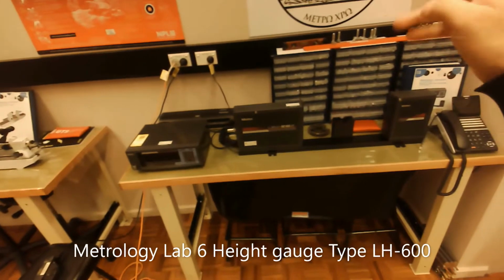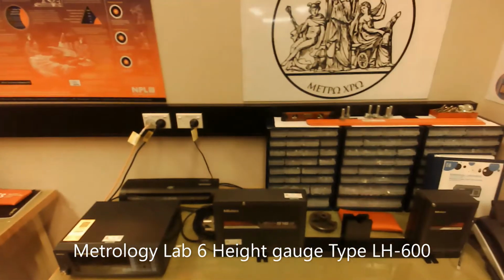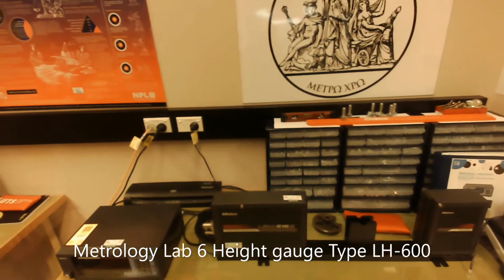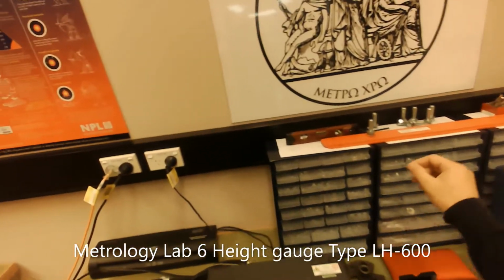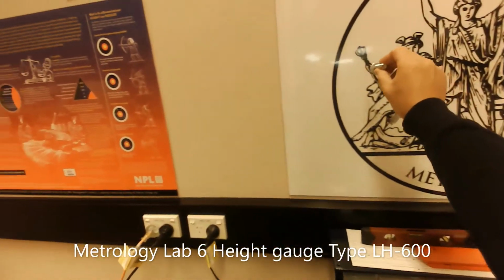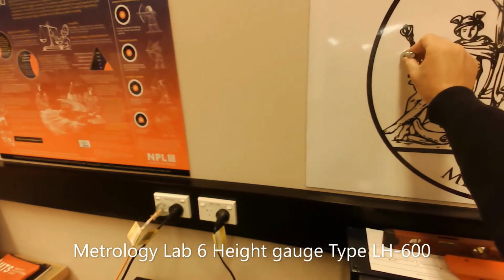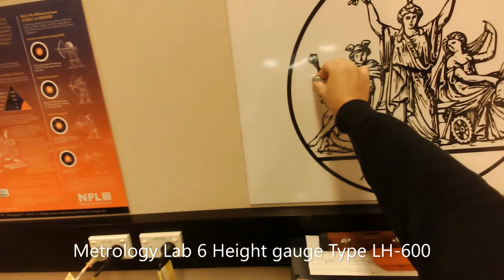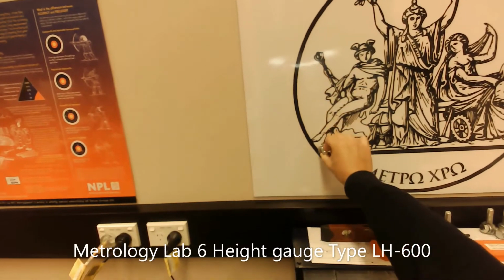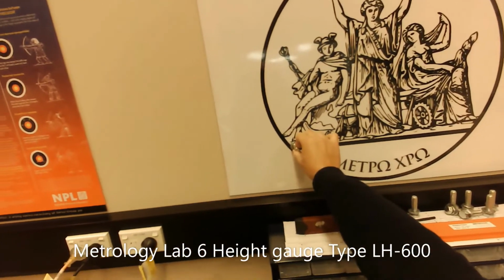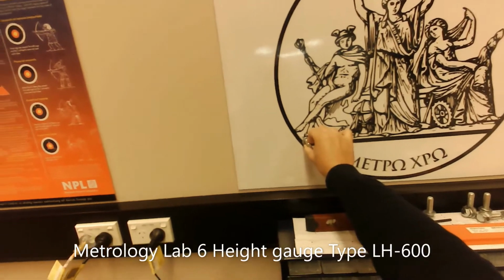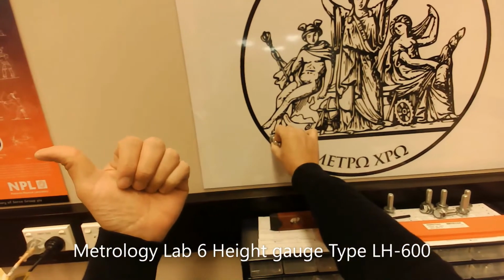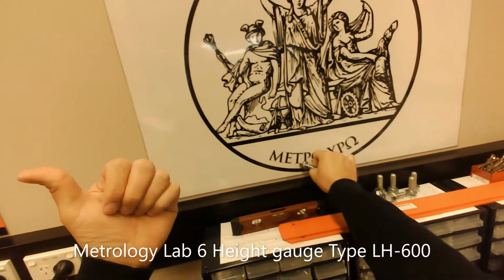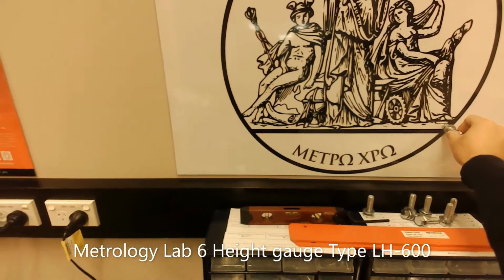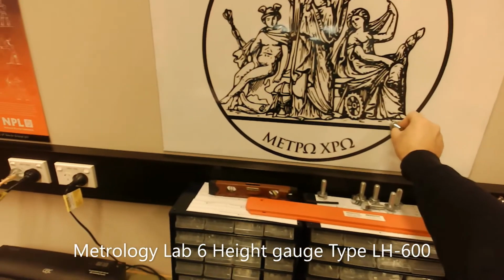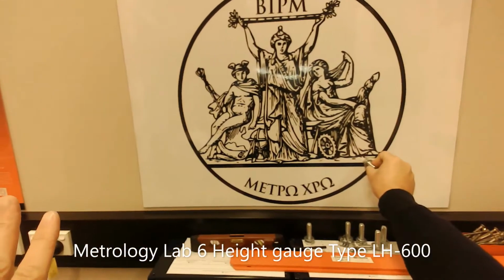Now, I usually use this image to show the student the movement we need to do for the probe. So what we're going to do is put the probe in a position like that. Then I'm going to press measure. The probe will go down to here. I'm holding the part firmly, and I'm going to hear the beep. When I hear the beep, I'm going to pull the part toward myself. The probe is going to move in this arc. When it reaches the same height, you will hear another beep. So you stop moving the part.